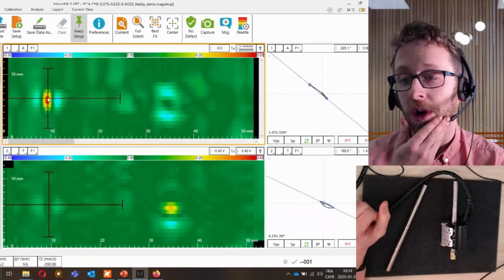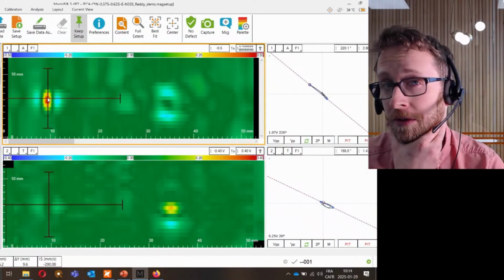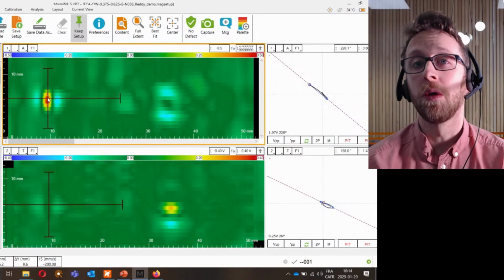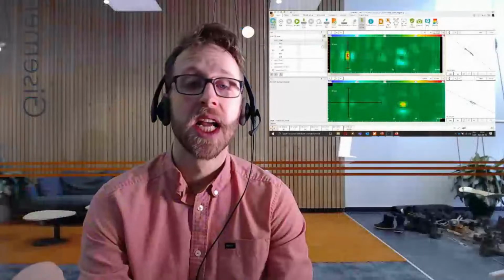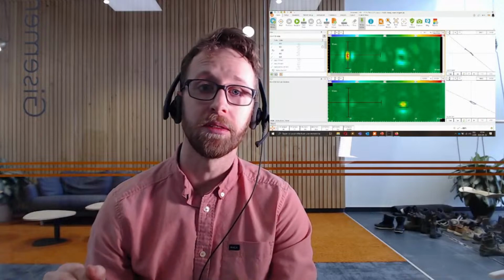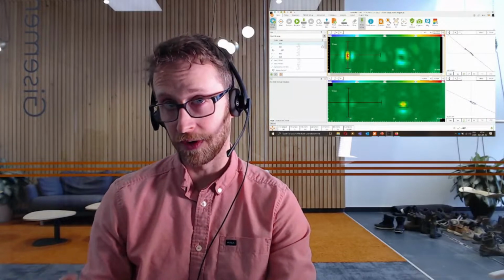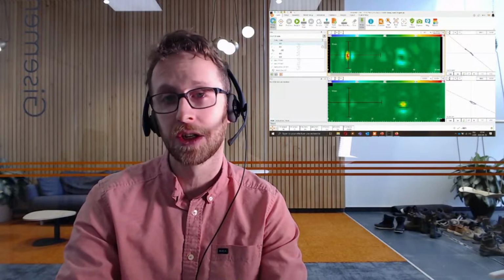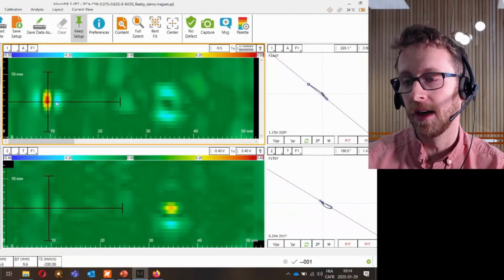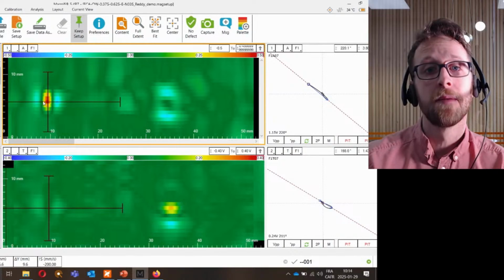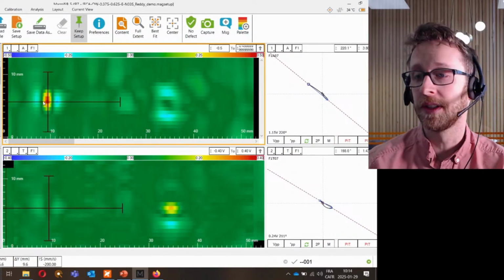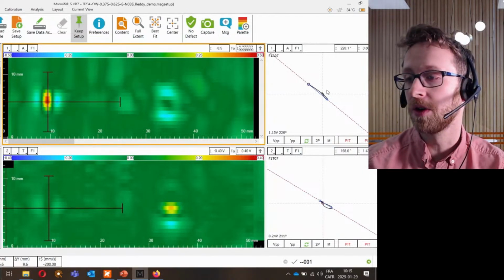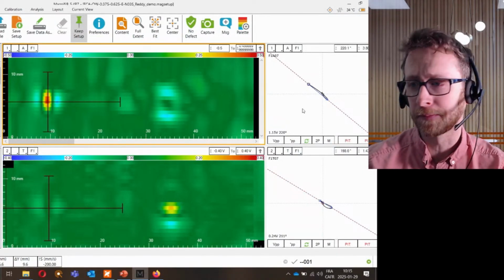So for those who are not familiar with the short double driver topology, that means that I have channels that are sensible only to axial defect, and I have another set of channels that are sensible to transverse defect. So on the top, I have my axial channel, and you can see in the C-scan, the red zone means that there's a defect here. So this is the vertical amplitude that represents the notch that we can see on the right side in my impedance plane.